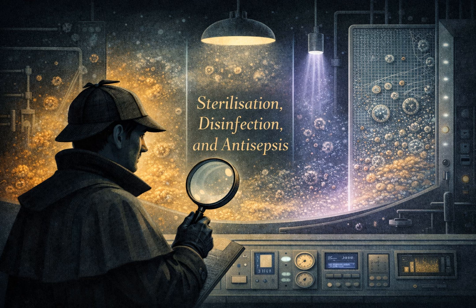Ready? Question 1. You have a set of surgical instruments. You accidentally set the autoclave to run at 100 degrees Celsius for 30 minutes instead of the required 121 degrees. Will these instruments be sterile? The answer is an emphatic no. Why not? 100 degrees Celsius is just the temperature of boiling water. It's great for killing vegetative bacteria, but it does not have enough energy to kill bacterial spores. To be considered sterile, you must kill the spores, and that requires 121 degrees Celsius under 15 psi of pressure.